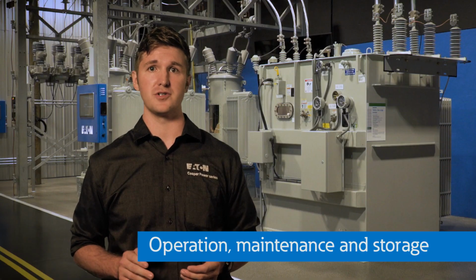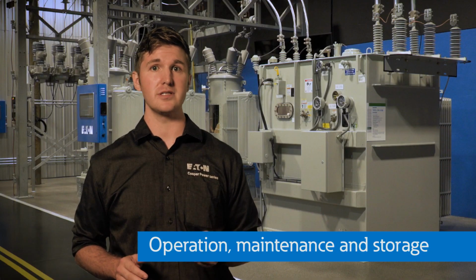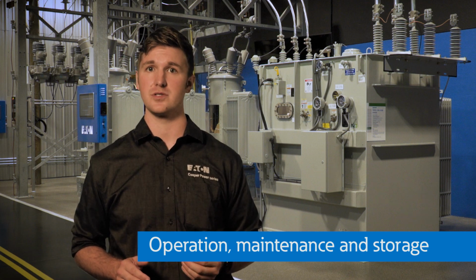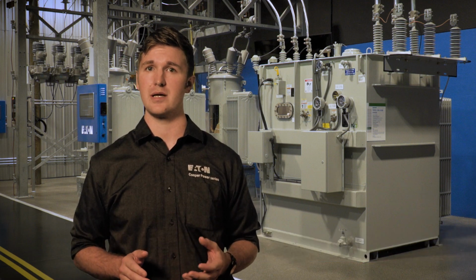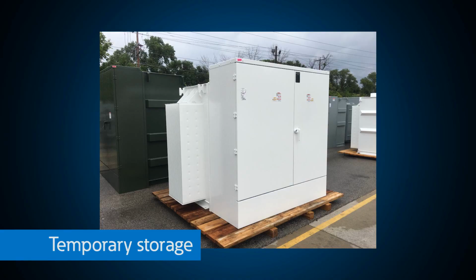Transformers, like all power distribution equipment, must be properly installed and maintained by competent personnel who have been trained and understand proper safety procedures. Eaton transformers are designed and manufactured to spend their lifetime outdoors. Oftentimes, a transformer is received before the site is ready for installation. Prior to installation, transformers may require temporary storage. Whenever possible, the transformer should be stored at its permanent location.